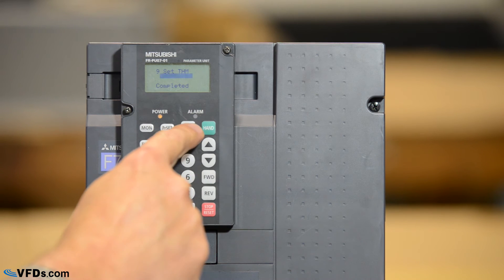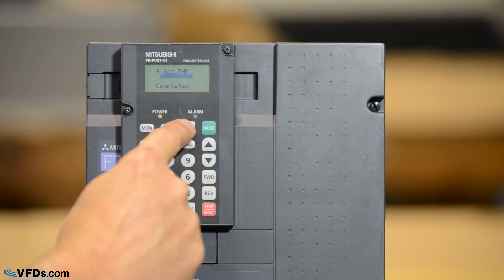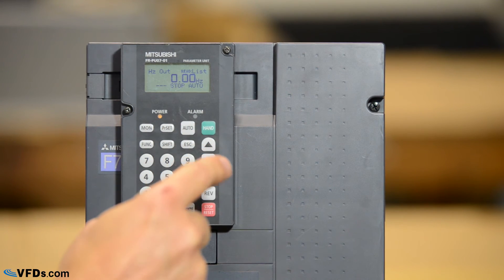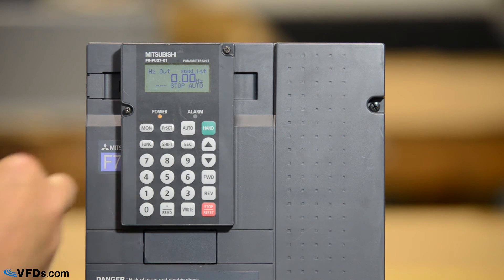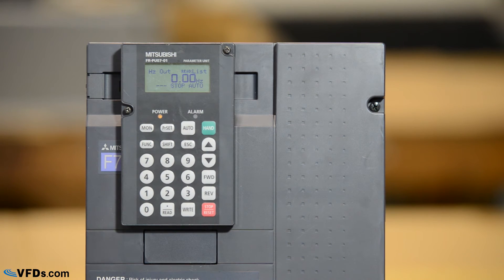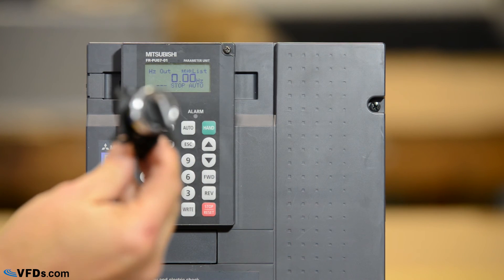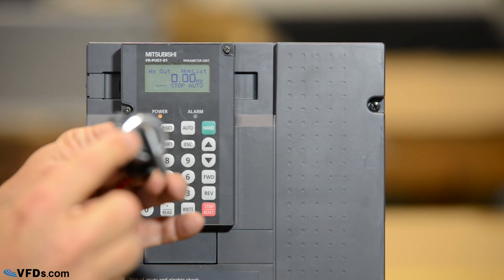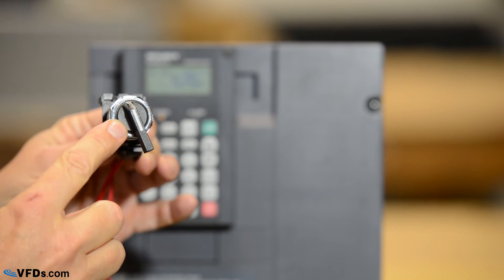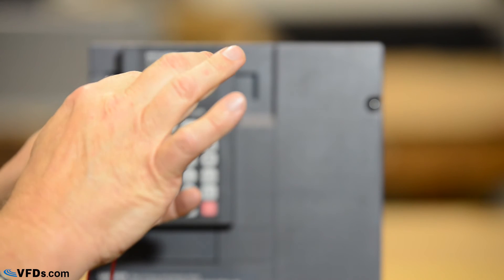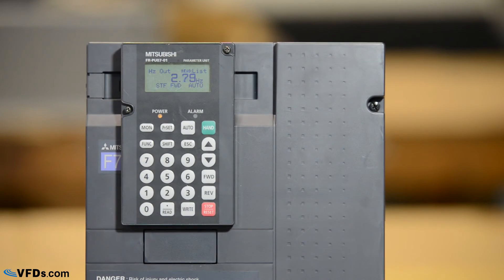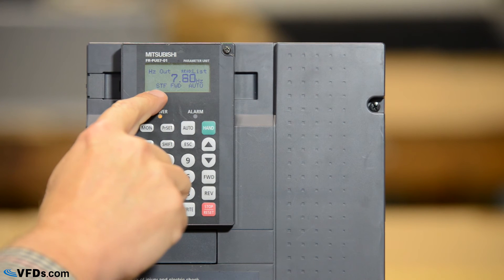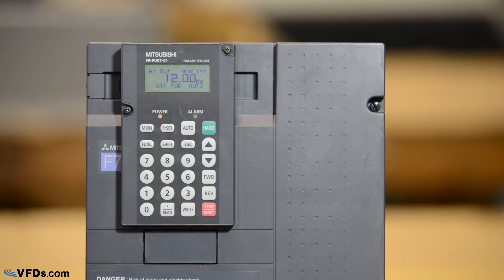Now I'm going to change to auto mode. When I press auto mode it transfers control to the digital inputs and the analog inputs into my drive. I have a switch wired up and we've wired this switch between STF that is start forward and common. So when we turn the switch on it shorts start forward and common. It tells us that we have a start forward command. You can see the frequency ramping up.